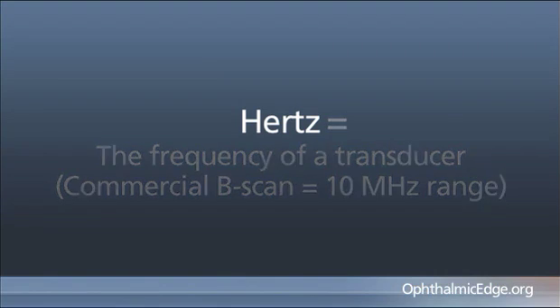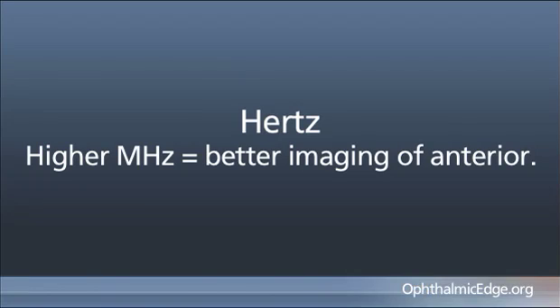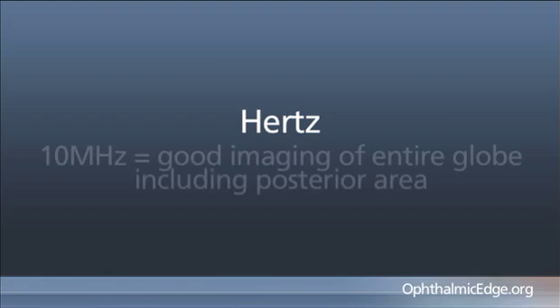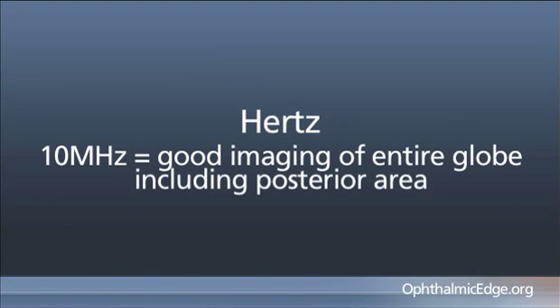You can certainly use higher frequencies, but the penetration into tissue is less. While you will improve the ability to see things in the front of the eye, you will lose the ability to penetrate much further back. The 35 to 50 to 80 megahertz instruments are basically for the cornea and anterior segment. We use 10 megahertz units for the posterior segment, but there are 22 megahertz units available that offer a compromise for both anterior and posterior segment work.